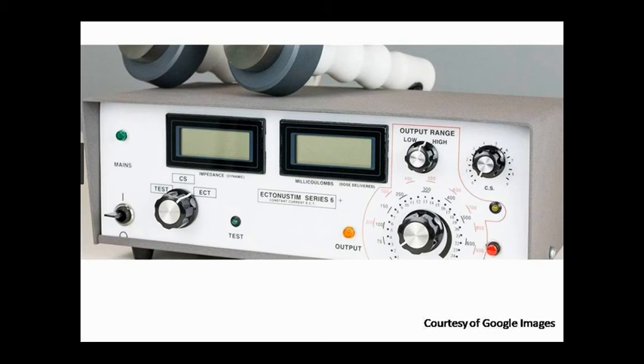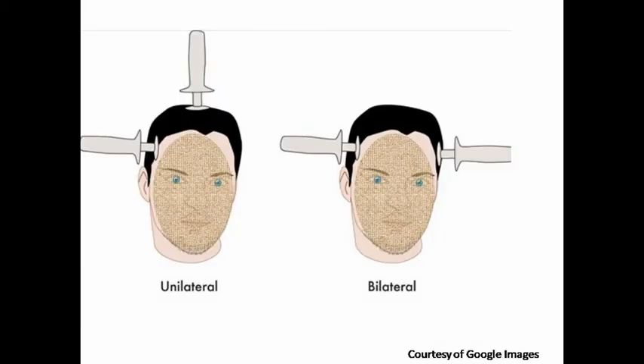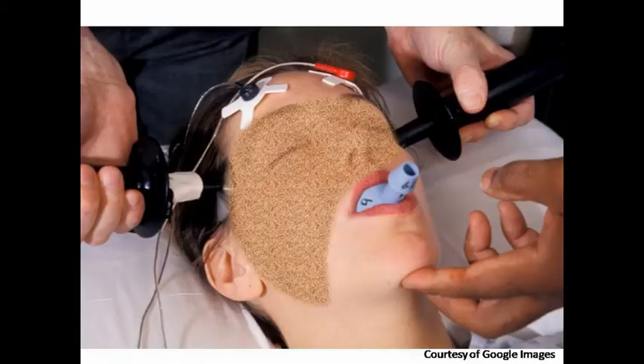The shock is applied through electrodes placed on either side of the patient's head, and an EEG is simultaneously recorded. The delivery electrodes can be a pair of manually applied paddles as shown here, or there may be a set of flat metal plates held in place by a tight rubber strap on either side of the patient's temples.